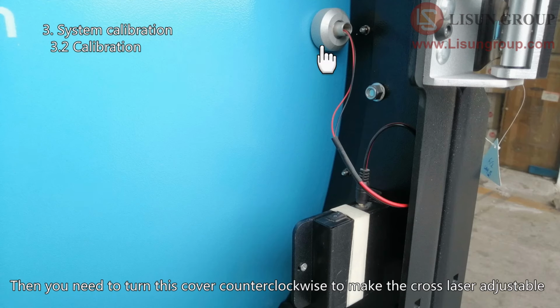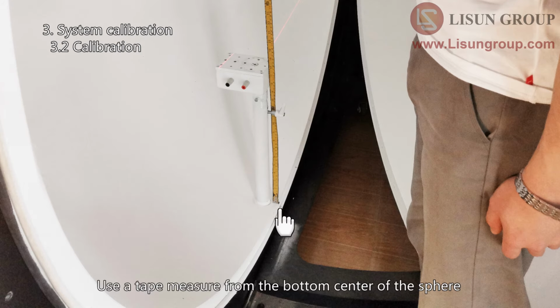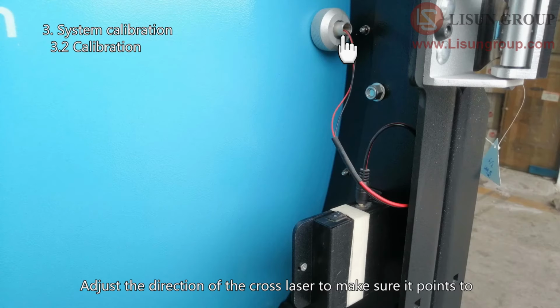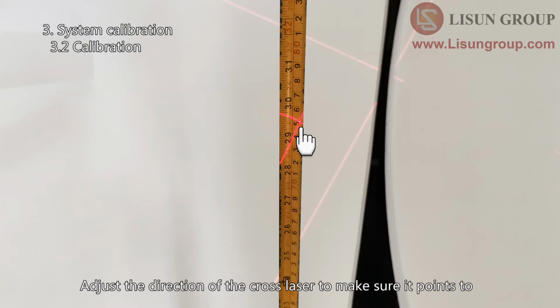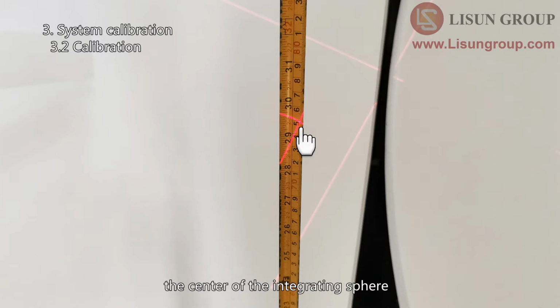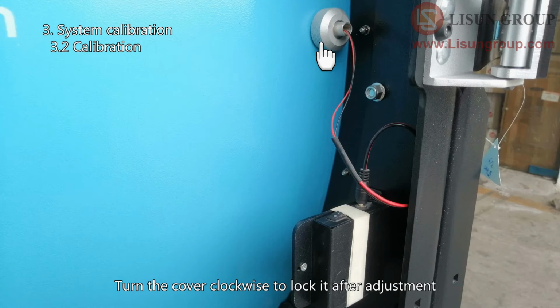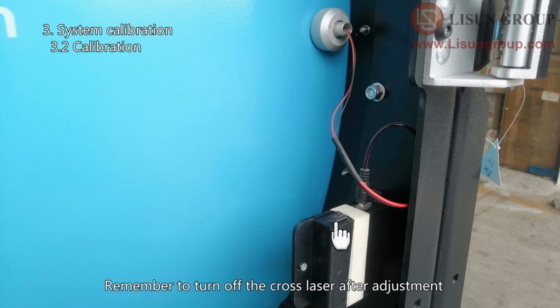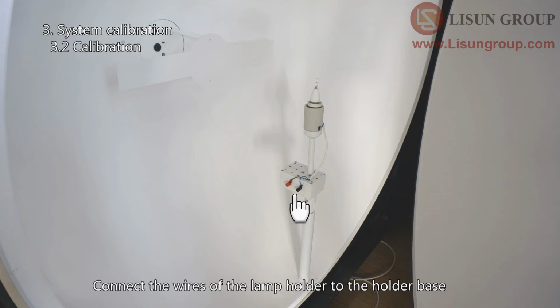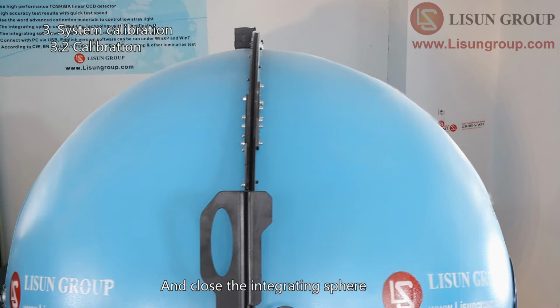Then you need to turn this cover counterclockwise to make the cross laser adjustable. Use a tape measure from the bottom center of the sphere. Adjust the direction of the cross laser to make sure it points to the center of the integrating sphere. Turn the cover clockwise to lock it after adjustment. Remember to turn off the cross laser after adjustment. Connect the wires of the lamp holder to the holder base and close the integrating sphere.